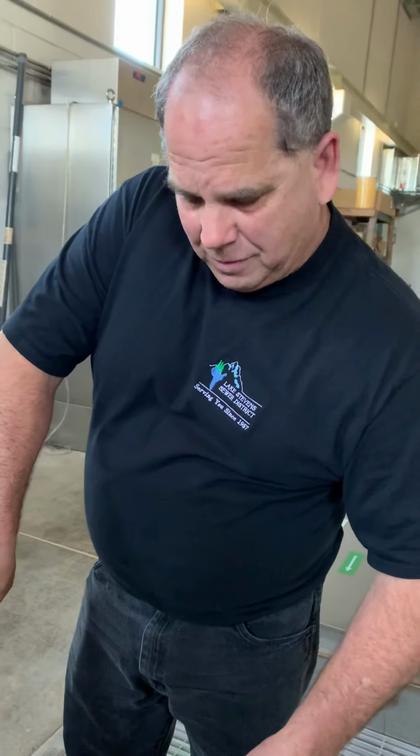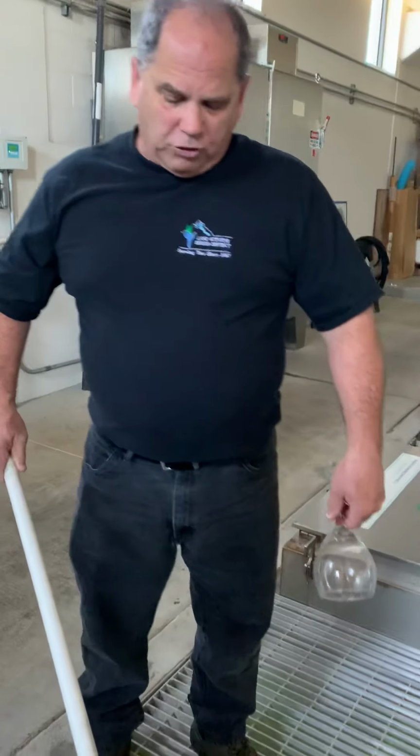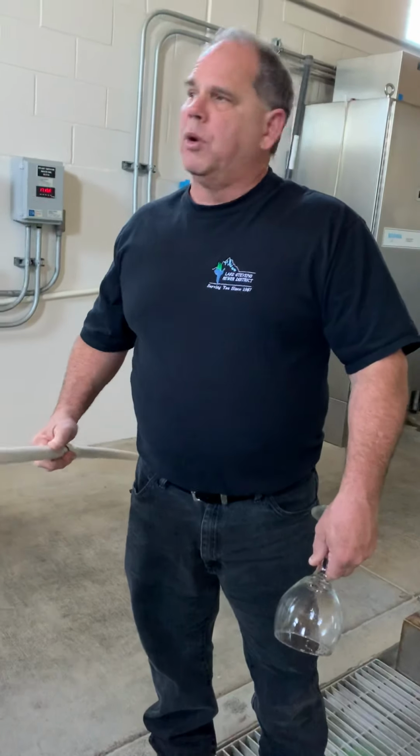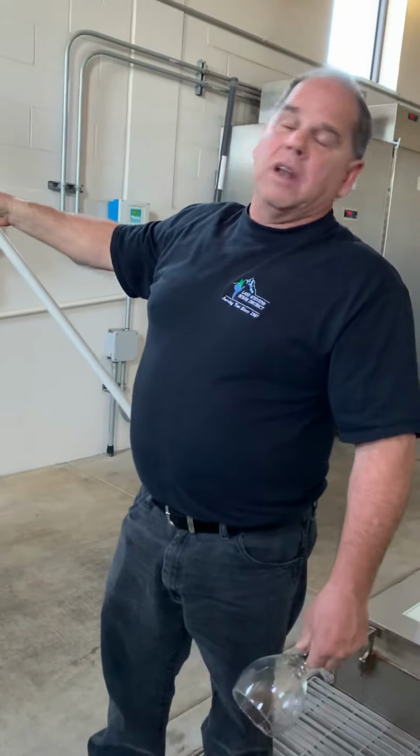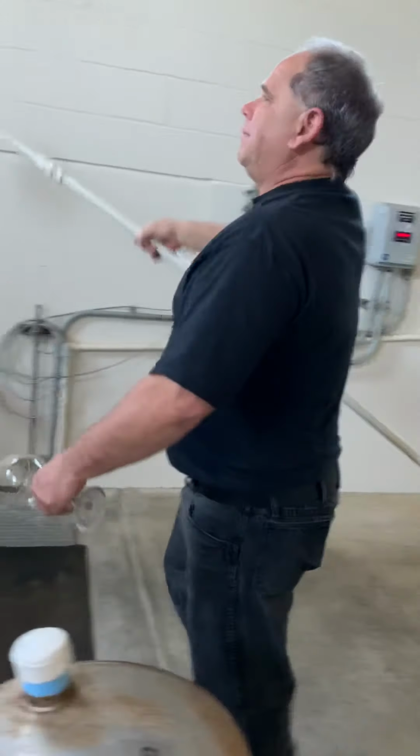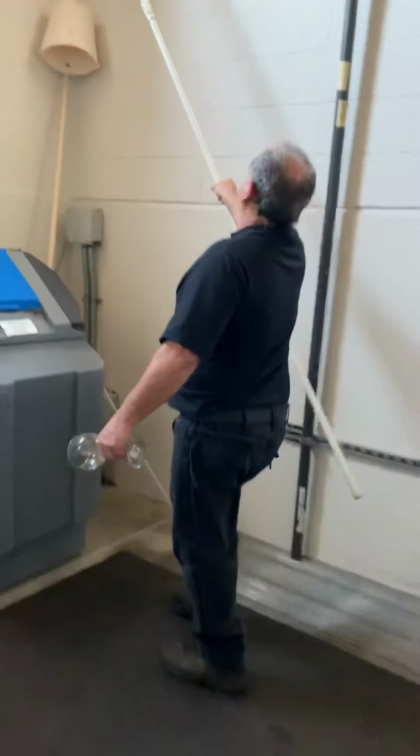It is cleaner than the slough that we put it into. We're putting in a super clean water, a neutral pH, no real nasties in it, just good stuff to put back in the environment, water the plants and the fishes. And this is a membrane treatment plant. That's what helps clean it so well. Membrane bioreactors, that's what does it. The membrane is head and shoulders above most treatment processes. Because of that, we can produce a very high quality effluent in a very small footprint. That's amazing. Thank you, Casey.